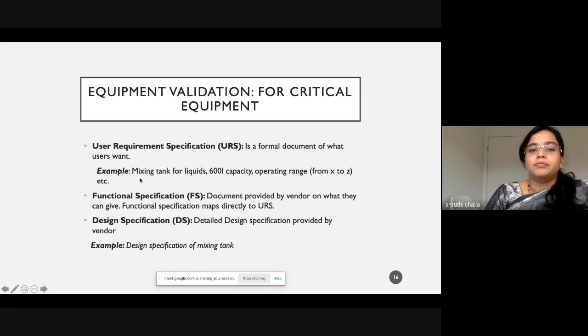Then once we get the equipment, we would install. We do installation qualification, we do operational qualification, and we do performance qualification. Installation qualification is a documented verification that a particular equipment is installed to comply with the design and manufacturer's recommendations. Operational qualification is a documented verification that a particular equipment functions as intended throughout the operation range. Performance qualification is a documented verification that a particular equipment can perform effectively and consistently to meet the product specification.